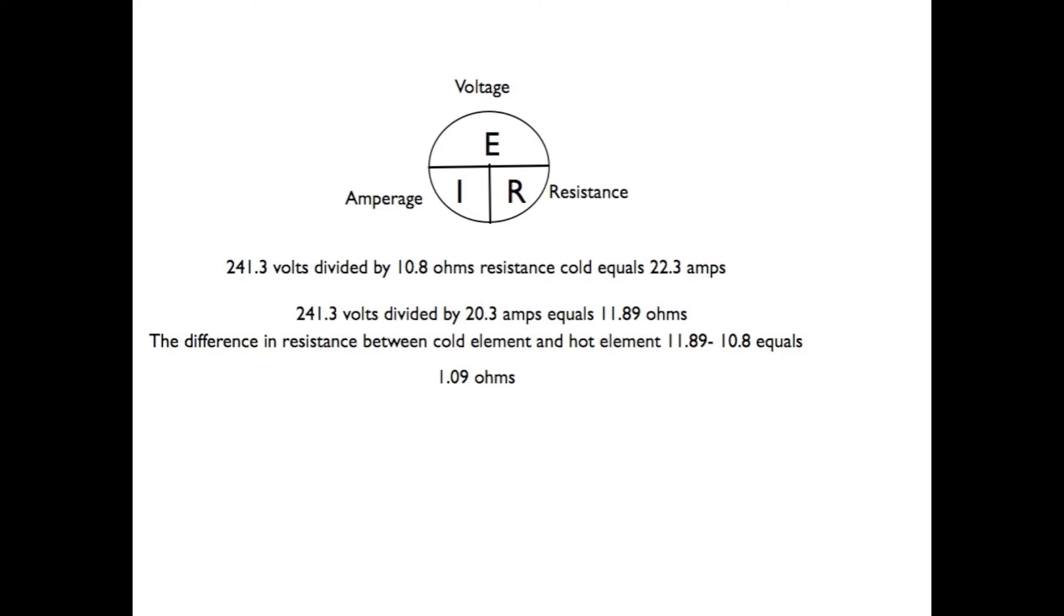Then we take the readings we actually got: 241.3 on the voltage again, and we had 20.3 amps. If we do the EIR calculation, we end up with the calculated ohms of 11.89. So the difference in resistance between a cold element and a hot element is 11.89 ohms minus 10.8 ohms, and it equals 1.09 ohms.